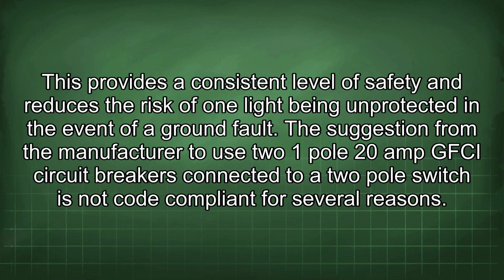This provides a consistent level of safety and reduces the risk of one light being unprotected in the event of a ground fault. The suggestion from the manufacturer to use two 1-pole 20 amp GFCI circuit breakers connected to a 2-pole switch is not code compliant for several reasons.